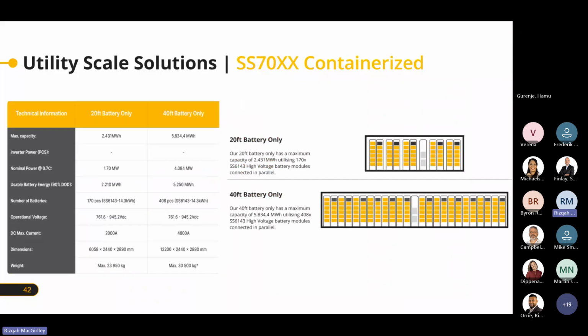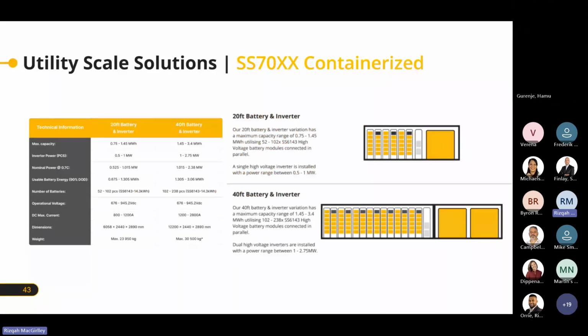This is just an overview of what we offer. The maximum capacity of our 20-foot battery-only container is 2.43 megawatt hours, and for the 40-foot battery-only container it is 5.8 megawatt hours. The 20-foot will utilize 170 of those SS6143 modules if fully packed with the maximum amount of batteries, but that's also dependent on your requirements, what inverters you're using, the capacity you need, and the configuration you end up using. The 40-foot battery-only container has 408 SS6143 high-voltage battery modules.